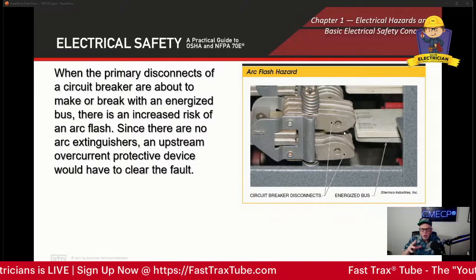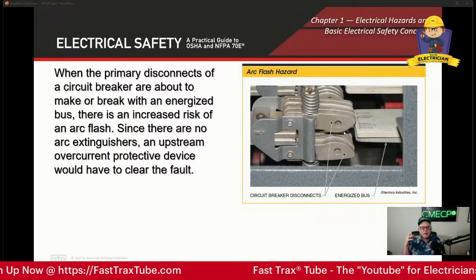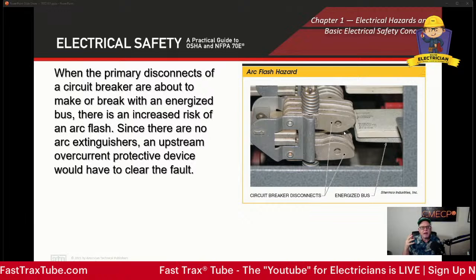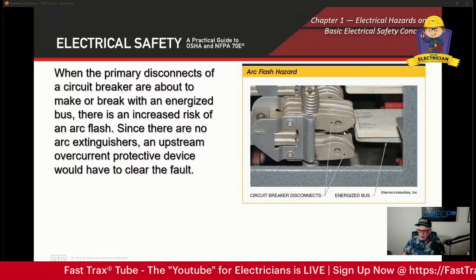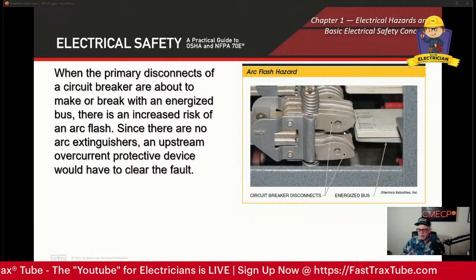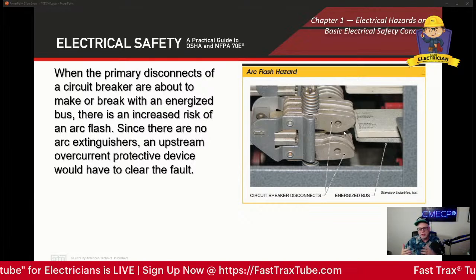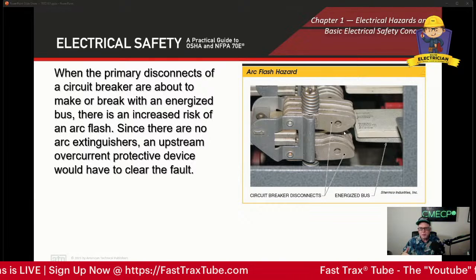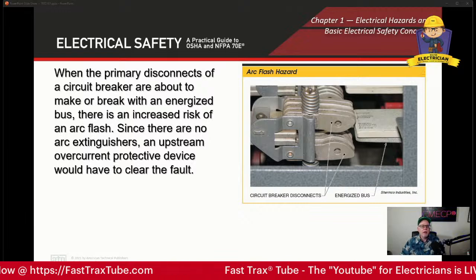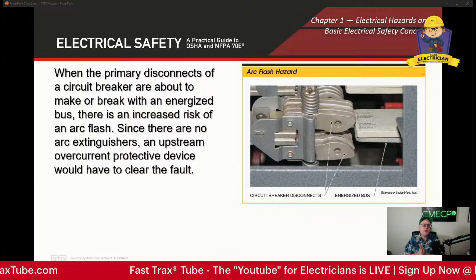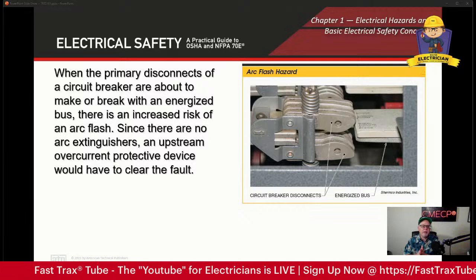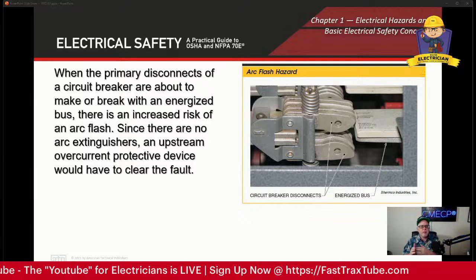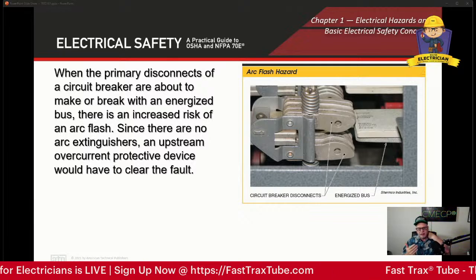The moment under load you break that contact, you create a potential arc. The intensity of that arc has a lot to do with the amount of current running through it, all those things being relevant. So when the primary disconnect of a circuit breaker is about to make or break with an energized bus, there is an increased risk of an arc flash, obviously.